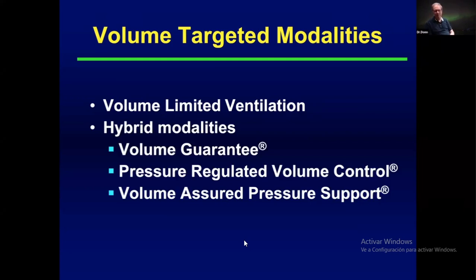There are hybrid modalities of volume targeting. Volume guarantee, I think, is probably the most popular and most utilized. There is pressure regulated volume control, and there is volume assured pressure support. Now, what all of these have in common is they're targeting a specific tidal volume to be delivered to the baby. But what's different is that they don't use this square wave flow pattern. They use an accelerating, decelerating pattern that is similar to pressure control or pressure support.